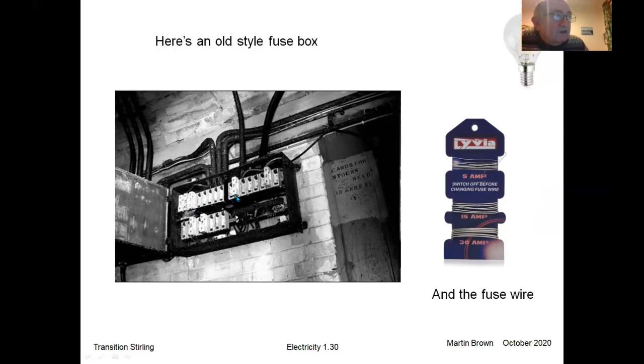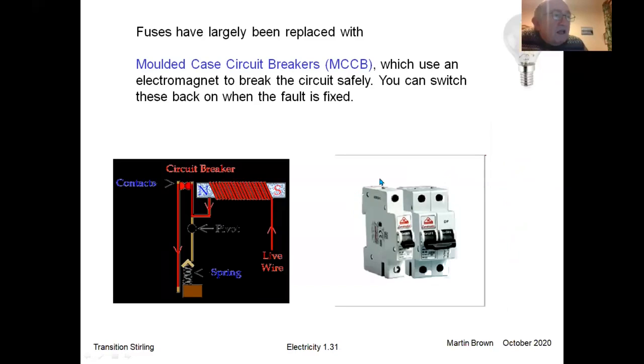Now, this is replaced by consumer units, as they're called, which have molded case circuit breakers in them. A molded case circuit breaker looks like a switch, but it's actually an electrically operated switch. If you push electricity through a coil like this, you can get a magnetic field, and if that current is very high, then the magnets will open the circuit automatically. It's not a very good drawing really, but you can imagine if this switch connection is magnetic and this creates a magnetic field, then this will pop open and open the circuit. So it's a magnetic system of fusing, if you want.